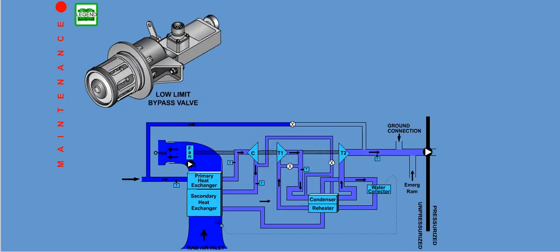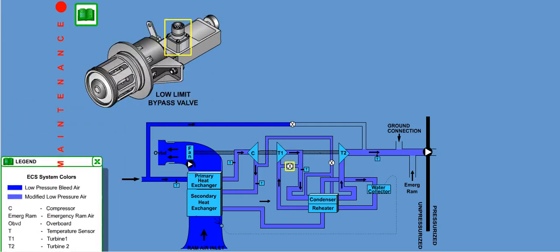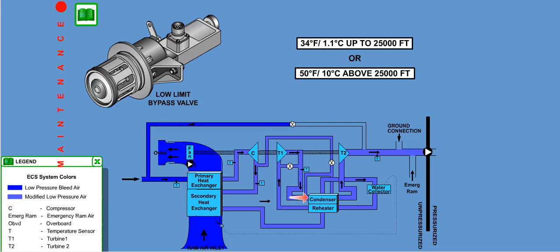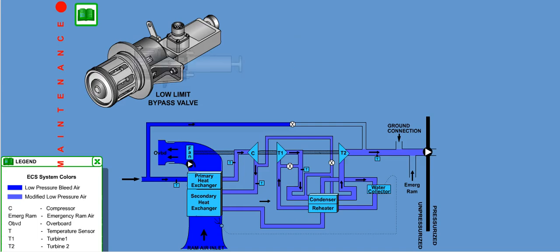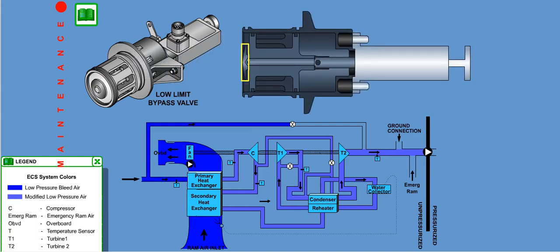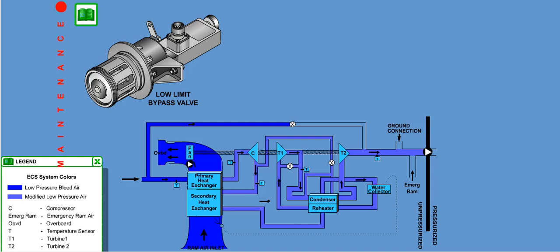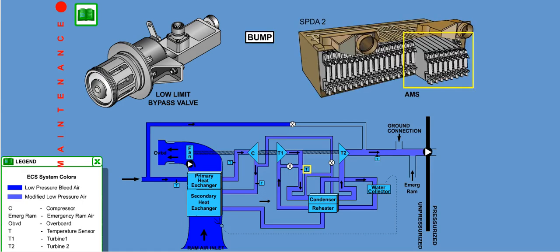The low-limit bypass valve is an electrically actuated valve installed in the air cycle machine turbine housing. The valve limits condenser inlet temperature to a minimum of 34 degrees Fahrenheit, 1.1 degrees Celsius, up to 25,000 feet, or to 50 degrees Fahrenheit, 10 degrees Celsius, above 25,000 feet. A linear actuator is used to rotate a piston that meters the amount of warm air bypass flow in order to control condenser inlet duct temperature. The downstream duct temperature is used as feedback for positioning of the valve. The AMS control logic is based on bump, stop, check, and the signal is sent to the actuator to extend or retract in steps. A knob on the linear actuator housing permits manual valve position adjustments.